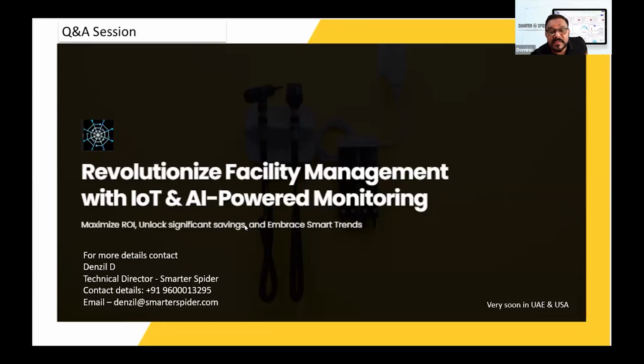Rishikesh Biswas ji is asking, where can we monitor priming and other system failures in the fire system? We have, for priming, the delta P sensor and water detection sensor, to check whether you have sufficient water, positive NPSH or negative NPSH. Most locations don't always have positive NPSH, the tank is below and the pump impeller is above the tank, so we definitely have to check the priming. We have the delta P sensor and water detection sensor for that, so yes, definitely we can check the priming as well.